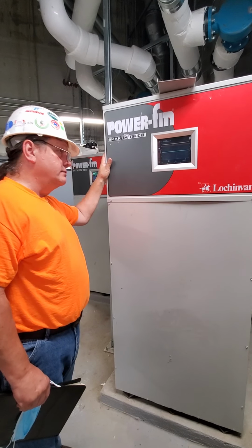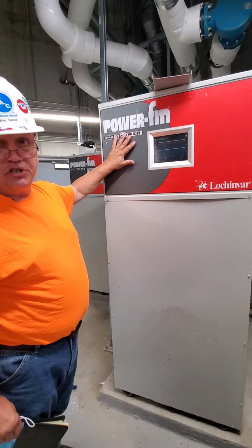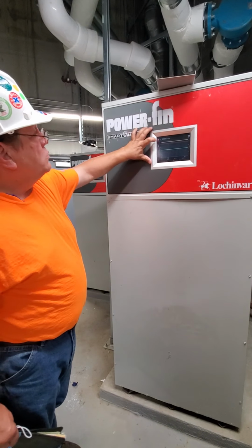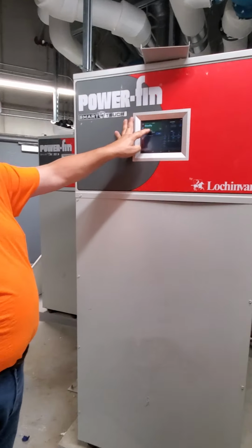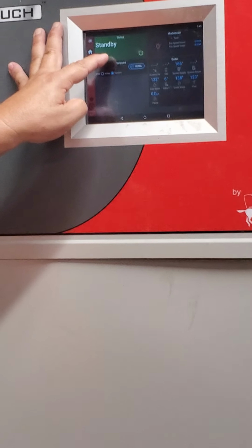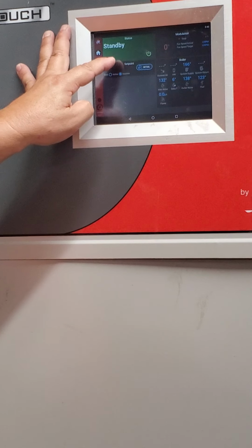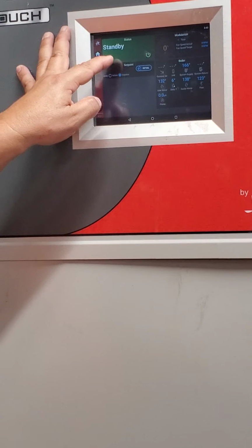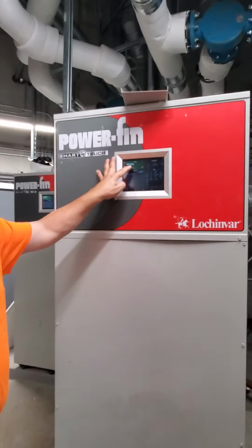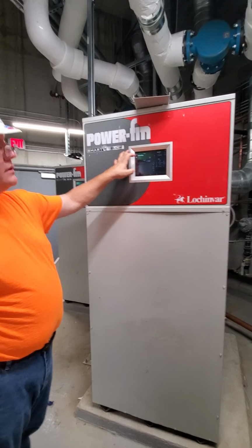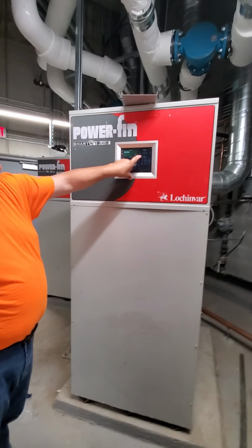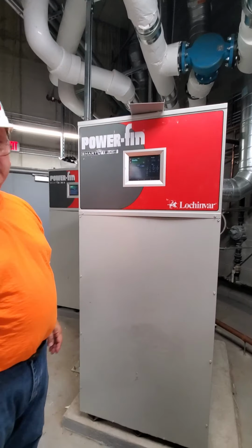You have a high and low gas pressure switch in there that it can trip out on. It will tell you back here in the home screen, this is running. This screen has more data on it and it changes in each mode it's in. It'll tell you when it's in pre-purge, it'll tell you when it's going to try for ignition, and it'll tell you when it's running. And it'll tell you over here at what percentage of firing rate it's at when it is running. So it can be anywhere from 20% to 100%. That's it.